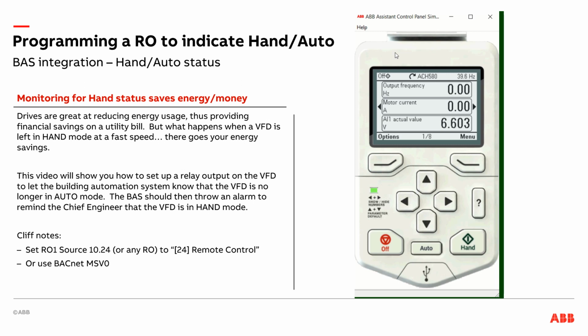So why would you care that the drive is in hand versus auto mode? Well, in auto mode, the drive is following the command from the building automation system. So when the demand is lower, the drive will slow down and save energy, save money on your utility bill. But sometimes something gets broken, maybe something's in a maintenance mode, maybe you need to override the automation system and a drive gets put in hand, which is a great short-term tool.